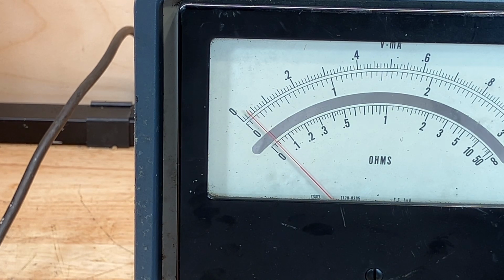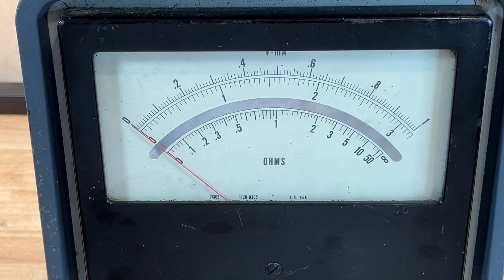Let me set it up with some voltage on the input and see if it responds. All right, with the unit put back together, sort of, enough to test it anyway, and with the power supply connected to the DC volts probe and the common terminal, it's set to the 1 volt range. Let's apply 1 volt to it and see what we get.